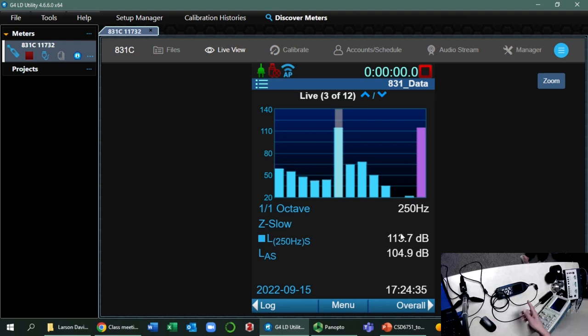So this sound level meter is actually not bad. I calibrated it when I got it. So if you compare to the calibrator, it's 0.3 dB off. Am I making sense? Ideally speaking, we should apply that correction factor. But for the sake of simplicity, let's just say don't worry about that. 0.3, anything less than a dB, really is not a big issue. Okay, so far so good for this acoustic calibrator. Good. All right, so let me unplug it.